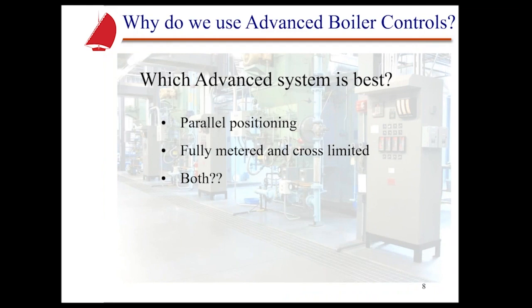So which system is actually best? If we're talking about parallel positioning, we also have to consider fully metered and cross-limited systems, or both. So what's the difference there? Well, with parallel positioning, we're basically setting up an air-fuel ratio curve based on those particular servos, if you will, or those valve positions, that air damper position. We establish where they're supposed to be open and how much to get a particular air-fuel ratio at different points through the firing rate range, okay?